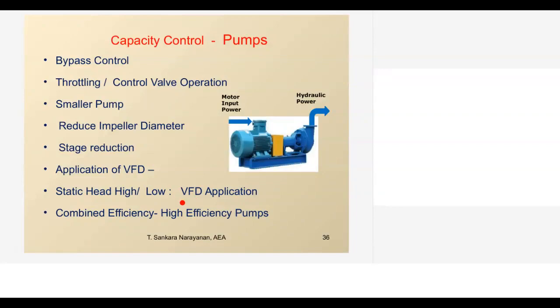Then as an audit, we have to always measure the combined efficiency of the motor and pump put together. The hydraulic power I can measure using a portable ultrasonic flow meter and head. On the input side I can measure the motor input power. So hydraulic power divided by the motor input power will give me the overall combined efficiency of the motor and pump. Normally the motor efficiency drop throughout its operation is very marginal, so we normally consider motor efficiency as per the nameplate. Then you can see what the combined efficiency is and how much it can be improved. Some pumping systems have combined efficiency of 30%, some can go up to 70%. So depending upon the capacity of the pump, we have to see what opportunities are there in a pumping network.